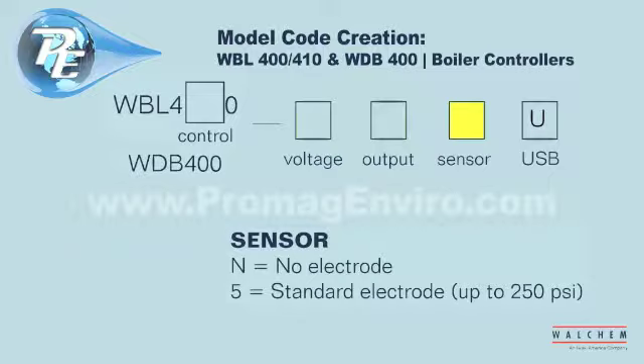The next selection is sensor. The letter N represents no electrode. The number 5 represents a standard electrode, rated at 250 psi at 392°F (17.2 bars at 200°C). The electrode material is 316 stainless steel and PEEK, with a conductivity range of 0 to 10,000 microsiemens per centimeter.